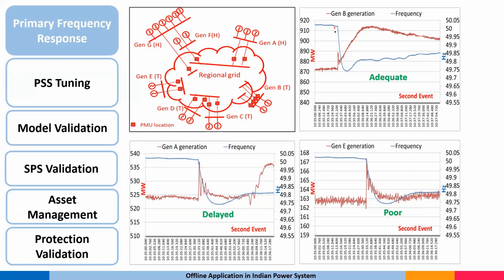So let us say this sudden drop is there, then the generators will increase their generation immediately to provide support to the system. Okay. So this is the common way the frequency response behaves. This is how the primary frequency response behaves in the power system, where the generators increase their generation up to their certain capacity, whatever limitation has been provided, so that the frequency can recover back. However, in some cases, we have seen that generators are not providing a good response.